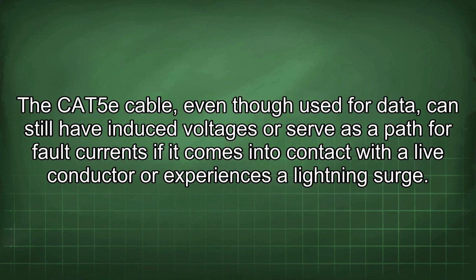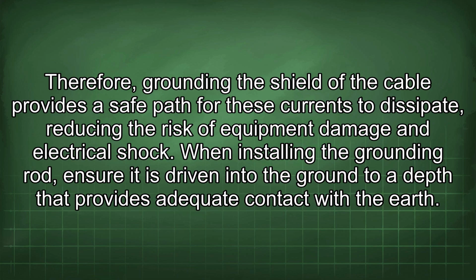The CAT5e cable, even though used for data, can still have induced voltages or serve as a path for fault currents if it comes into contact with a live conductor or experiences a lightning surge. Therefore, grounding the shield of the cable provides a safe path for these currents to dissipate, reducing the risk of equipment damage and electrical shock.